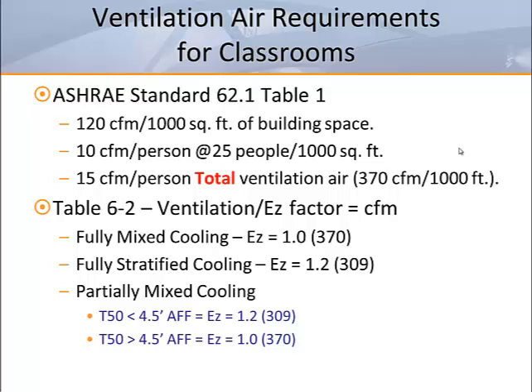ASHRAE Standard 62.1 covers ventilation for acceptable indoor air quality. For school classrooms, Table 1 prescribes 120 CFM ventilation air per 1,000 square foot of space. Add to that 10 CFM per person. When the occupancy rate is not known, the default occupancy is 25 people per 1,000 square feet, or an additional 250 CFM of ventilation air.